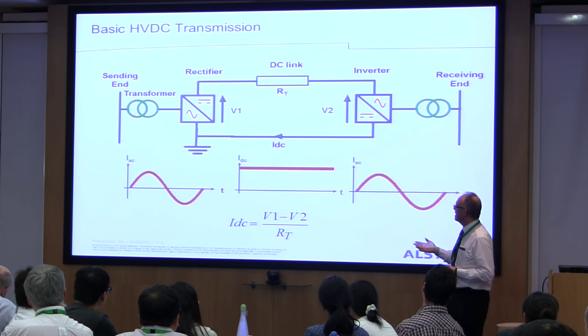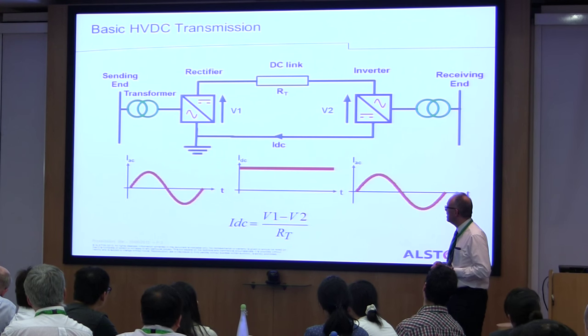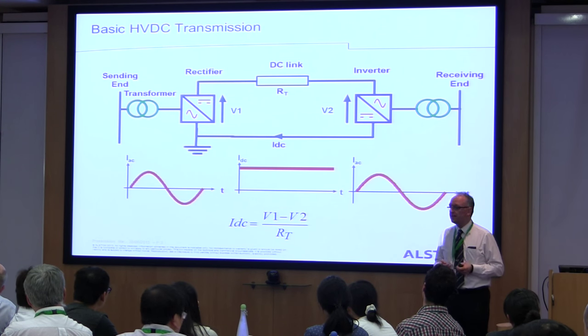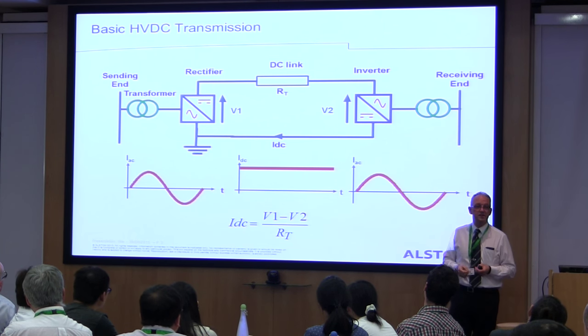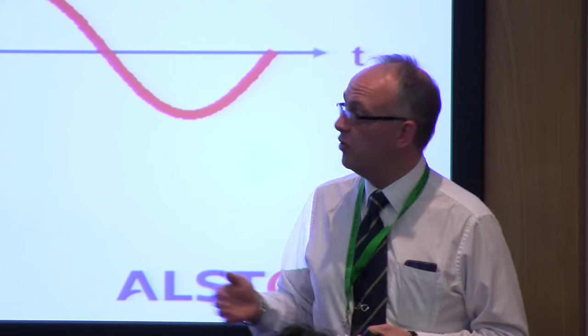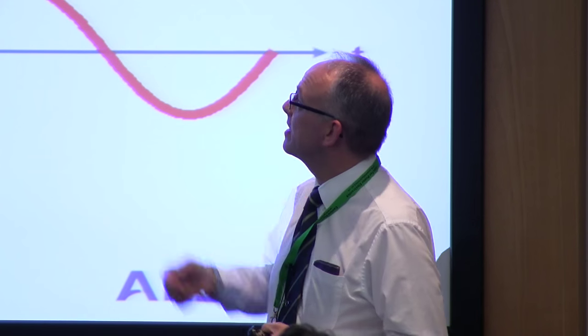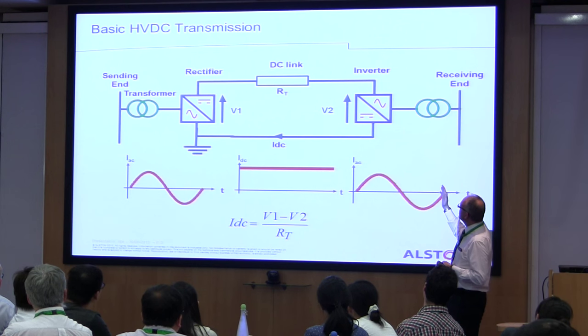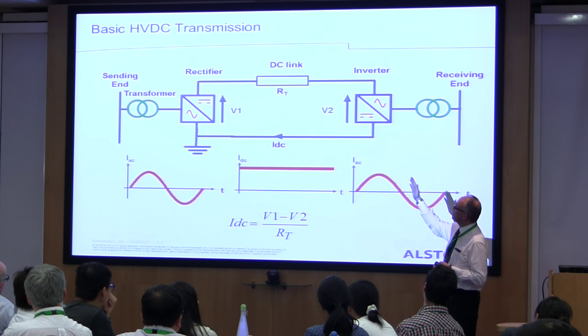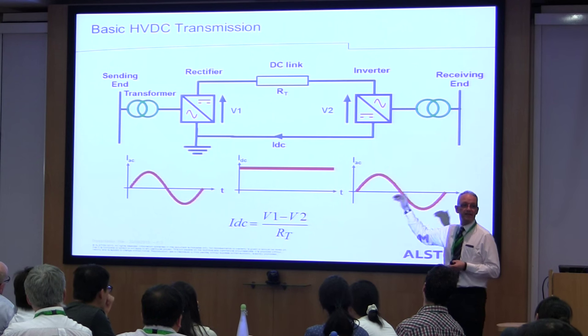The way we normally control an HVDC link is to make one converter responsible for controlling the DC voltage on the link, and the other converter controls the current. We normally pick a compounding point — typically the point of maximum DC voltage, which is the DC terminals of the rectifier. The inverter typically controls the DC voltage as it sees it at the rectifier, taking into account the resistance of the transmission line and the current.